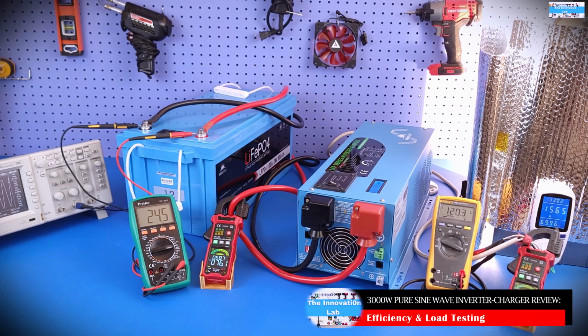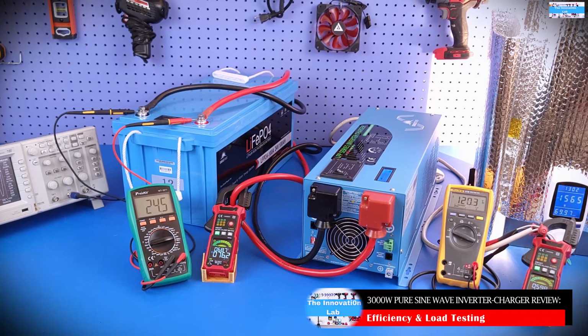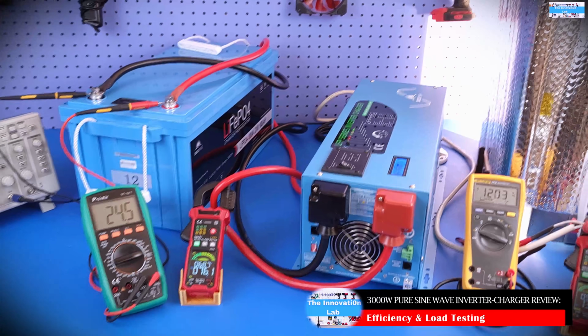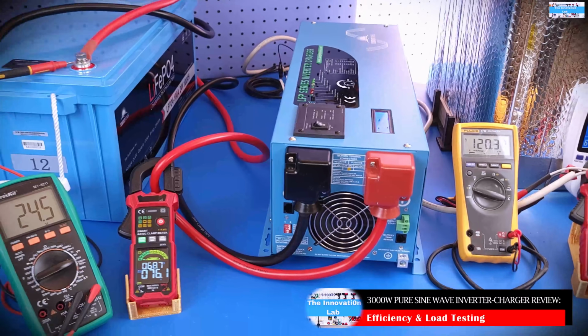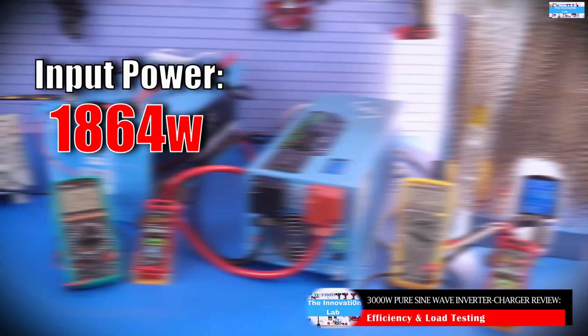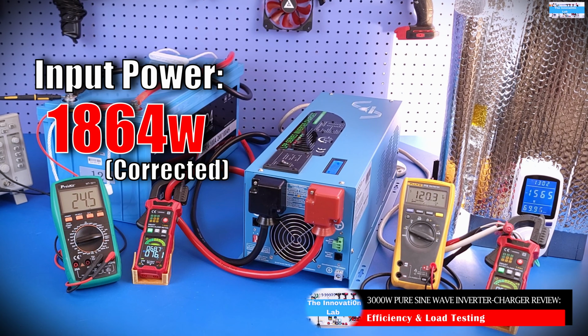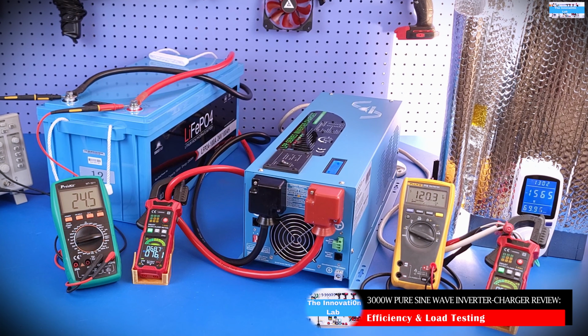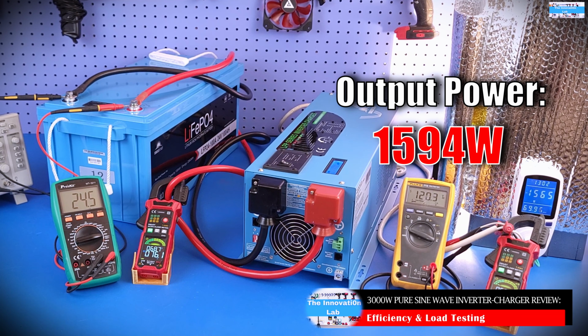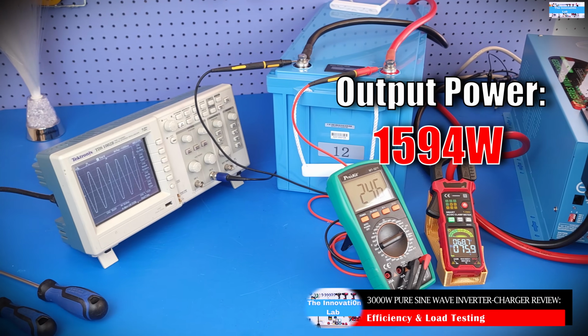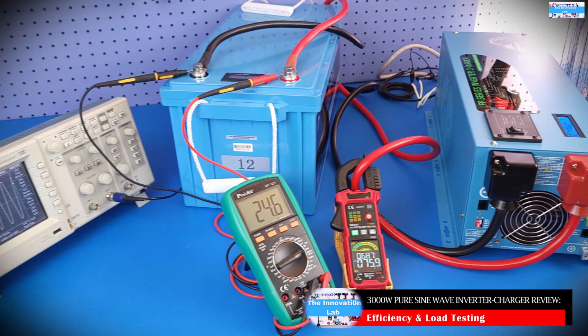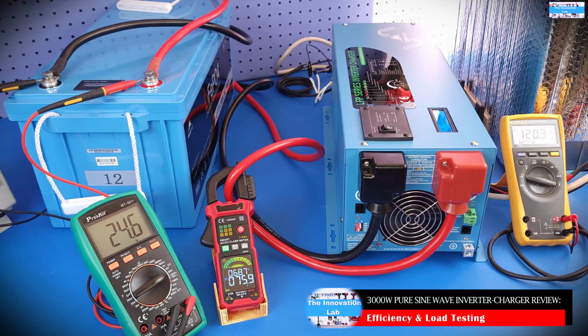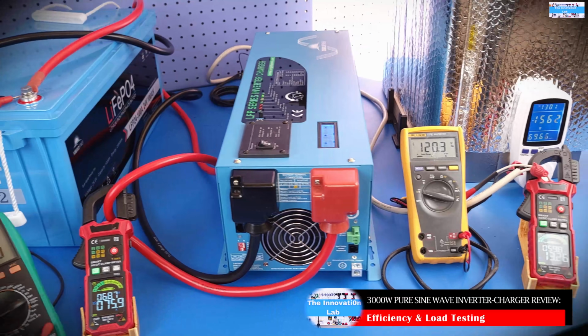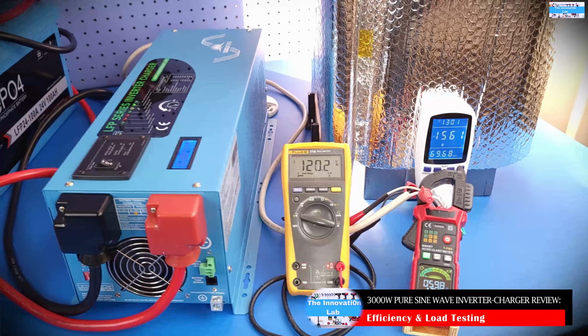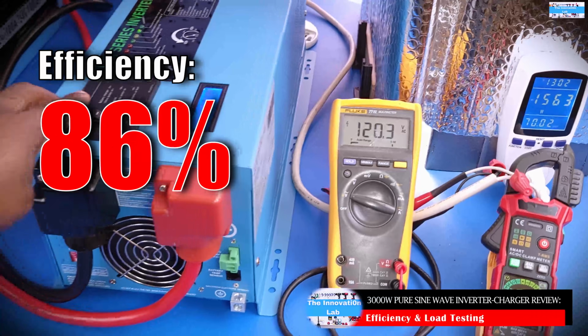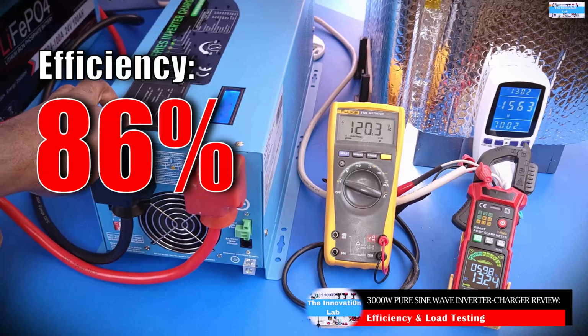Looking at our DMMs and current probes, we saw an overall input power coming from the battery to the power inverter system of about 1867 watts, and an output power of about 1594 watts when we do the math. We also have to account for a cable loss of about 20 watts, given that we measured a small voltage drop between the battery and the power inverter. This power inverter gave us an efficiency of 86%.